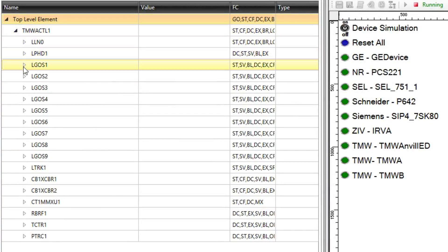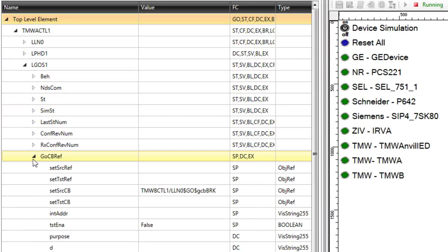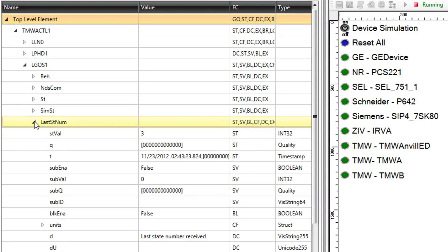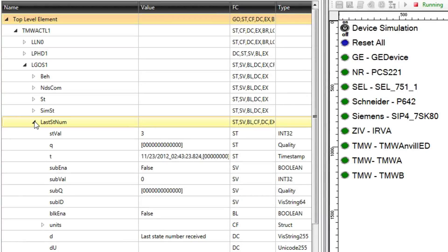Taking a closer look at LGOS1, the GoCBref.setSourceCb data attribute shows that it monitors a Goose stream published by BeagleBone TMWB. The last stnum.stval is the last state number received in a Goose stream in the GoCBref.setSourceCb. The Goose publisher will increment the state number when any data attribute in the dataset changes.